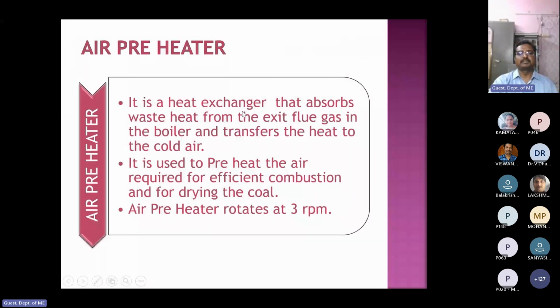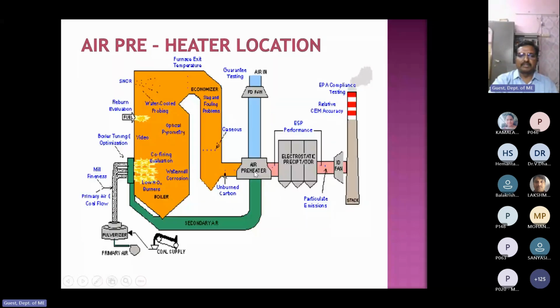It is a heat exchanger that absorbs waste heat from the exhaust flue gas in the boiler and transfers the heat to cold air. Here we are using two types of air: primary air and secondary air. Primary air is for transferring the fuel to the boiler, and secondary air is for complete combustion of the fuel inside the furnace. This is the location of the air preheater, which supplies the air to the furnace directly from the FD fan. The primary air is shown here in this diagram. After the air preheater, flue gases enter the ESP before going to the chimney.